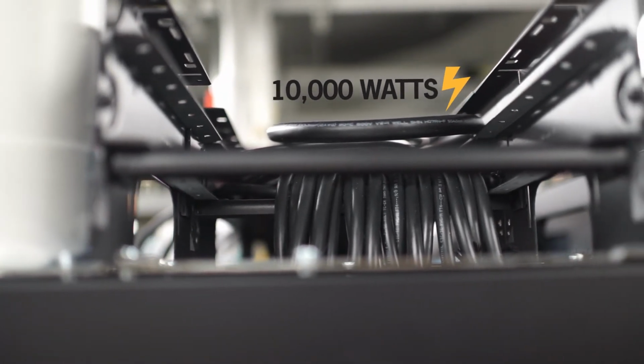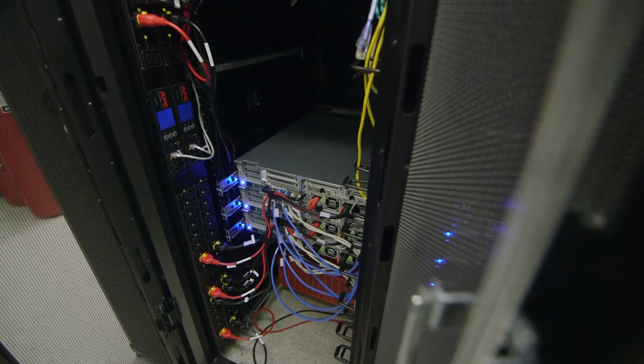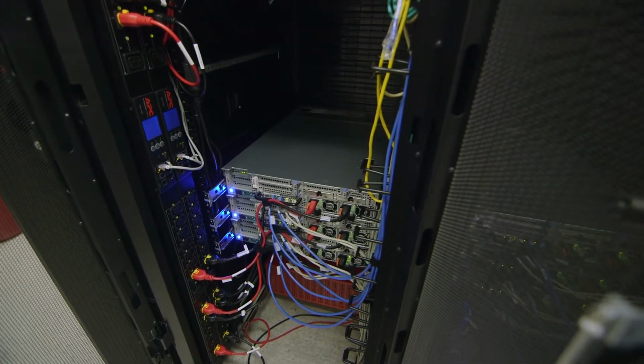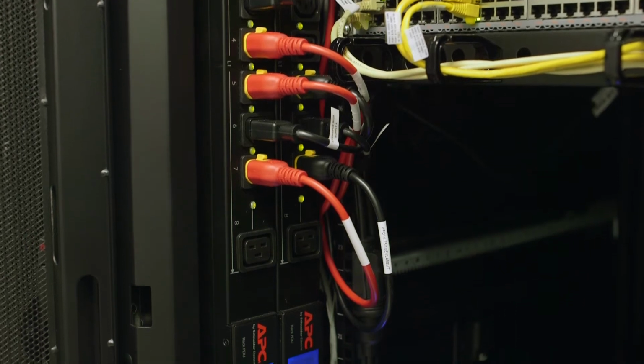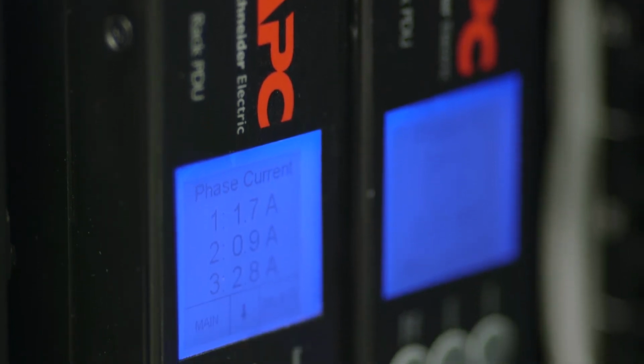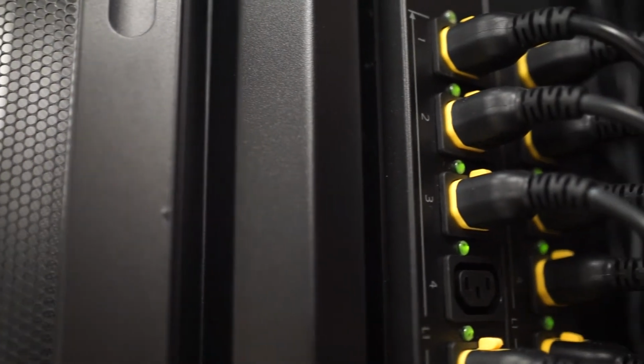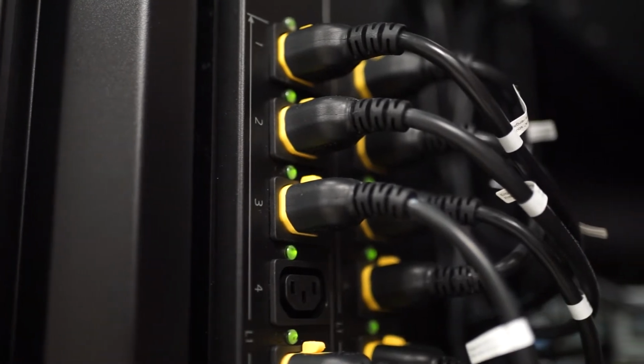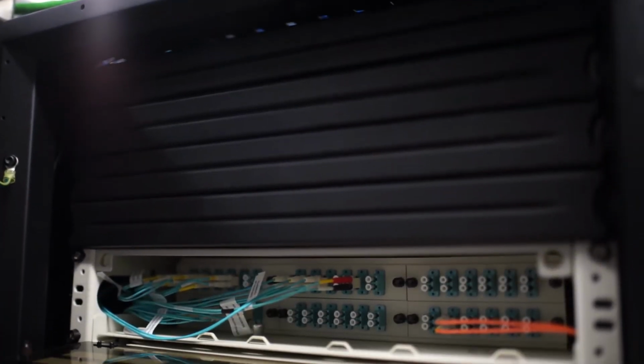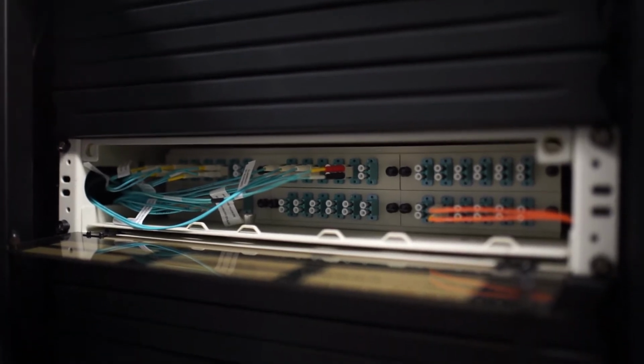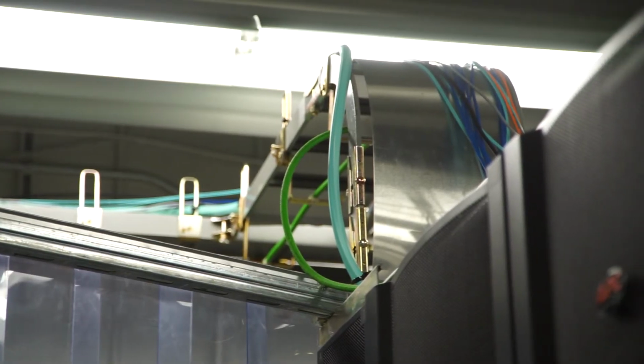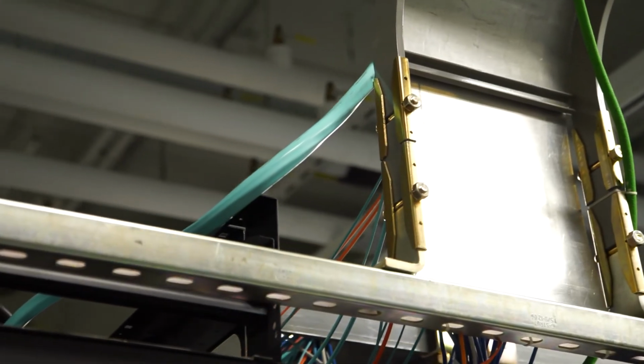The power distribution was configured with about 10,000 watts of power available to each cabinet, with each one having redundant power distribution units, or PDUs. These PDUs are technically sophisticated power strips that have power from distinct UPSs available to each cabinet. Because of this, each device within a cabinet would have redundant power supplies and redundant cabling to each of those PDUs. DC-1 is also connected with multiple independent fiber pathways, allowing you to connect to your data via the internet or by private E-line connections to a particular site. Therefore, if one path becomes unavailable, another pathway is still active to access your data.